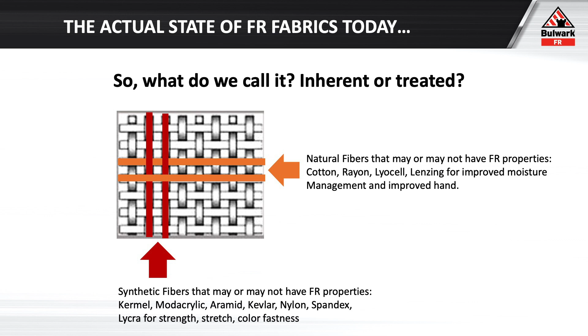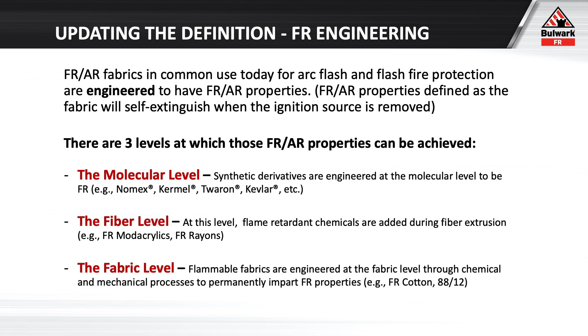There are no rules for us to market that to you as end users. What you really need to understand is there are three ways commonly practiced to provide a flame-resistant, arc-rated solution. I can change the molecular formula of a synthetic and it will not support combustion. I can add FR chemistry at the fiber level when it's still a soup and extrude an FR fiber. At the fabric level, I can introduce chemistry that will bond to that cellulosic for the life of the garment so it will not support combustion through charring.